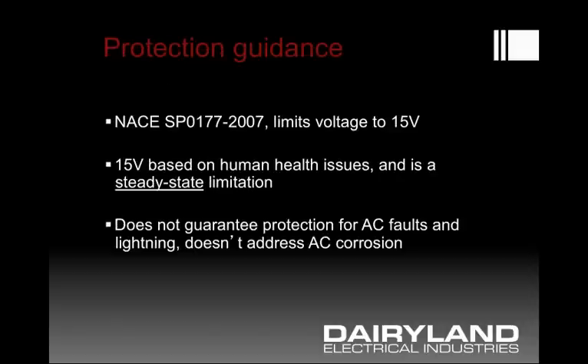There are additional guidance documents and criteria for overvoltage protection. The NACE document SP0177 recommends limiting voltage on pipelines to 15 volts. Keep in mind that 15 volts is a human health risk and is basically a steady state condition — it doesn't guarantee protection for AC faults and lightning. A totally separate topic is any level of mitigation needed to address AC corrosion. So keep in mind, this is steady state conditions, the kind of conditions where you could go out with a meter and measure at any particular point in time — not fault conditions.